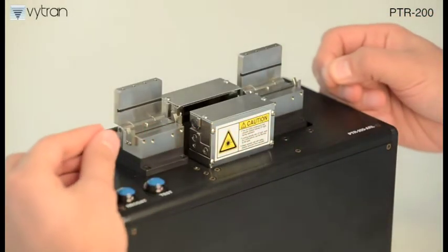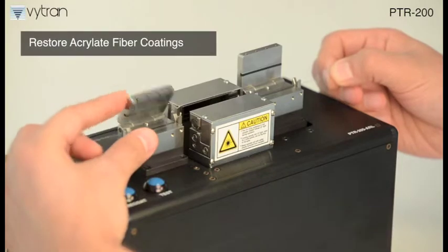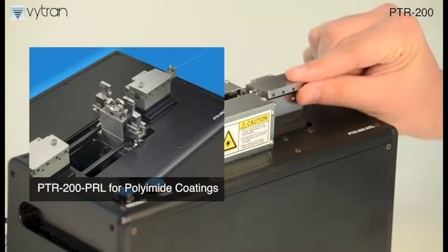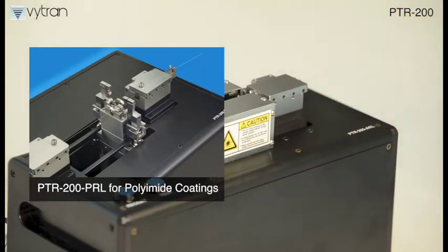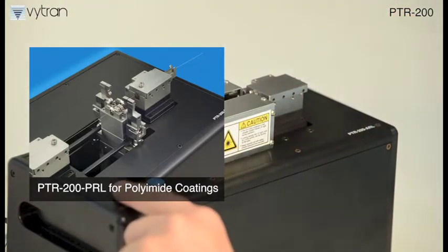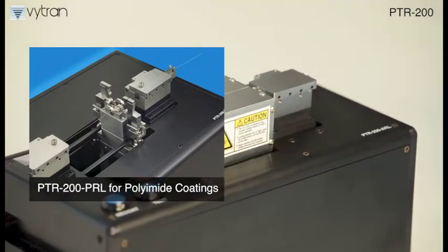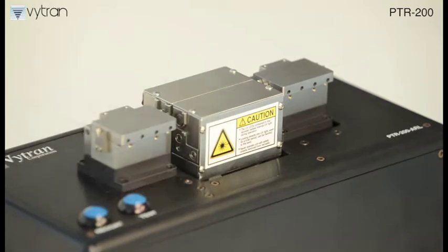Vytran's standard PTR-200 recoaters are designed to restore acrylate fiber coatings. We also offer a special PTR-200 unit, the PTR-200 PRL. The PTR-200 PRL is a unique system that uses a thermal curing process to restore polyimide coatings.